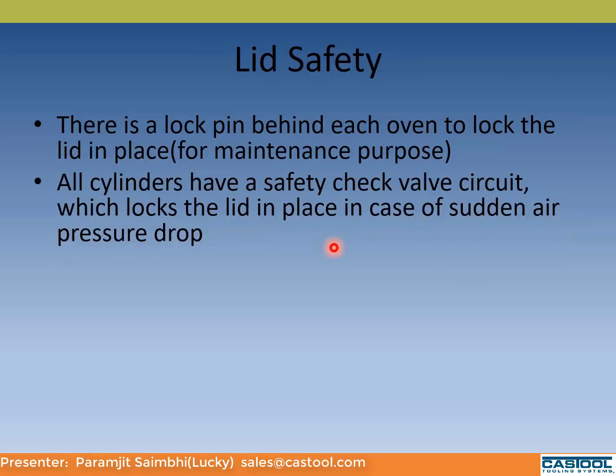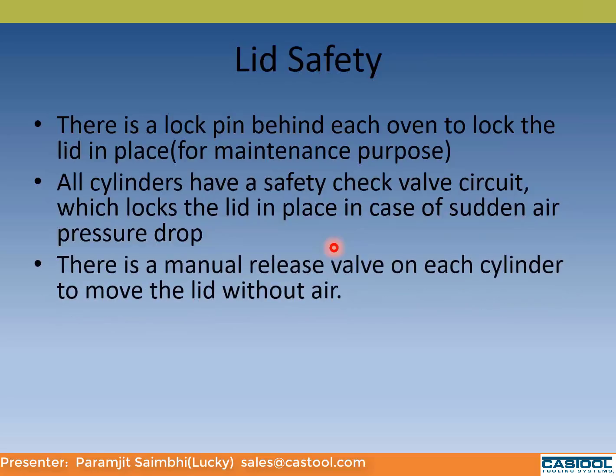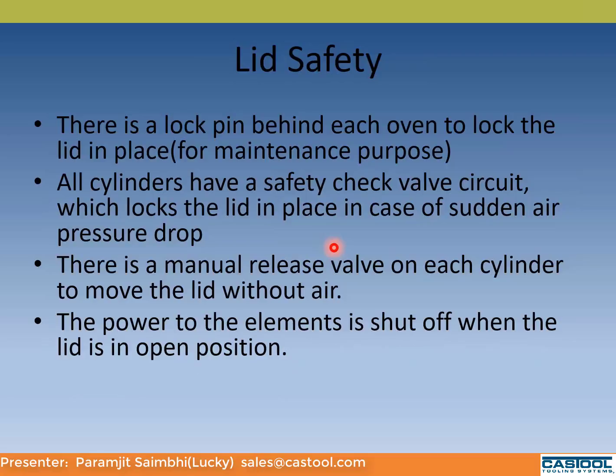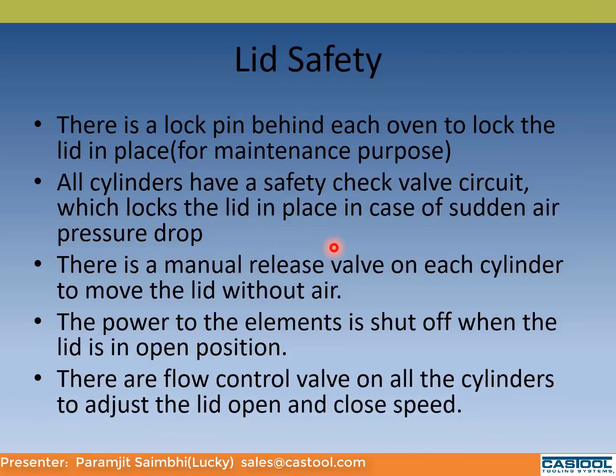There's a check valve on each cylinder to lock the lid in place in case of sudden air loss, so the lid never drops on anybody and hurts people. There's a manual release valve. I'll show you in another slide where you can press that and release the air pressure and open and close the lid if you don't have any air pressure available. The power to the heating elements is shut off when the lid is in open position. So we're always monitoring that. There's a sensor on each cylinder. And there are flow control valves on the cylinders to adjust the speed of open and close.